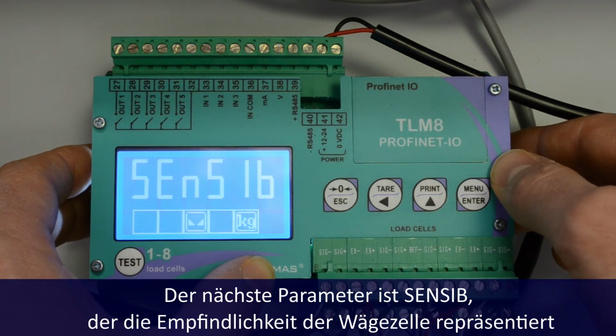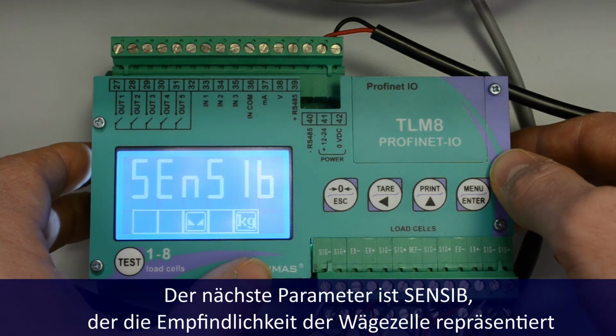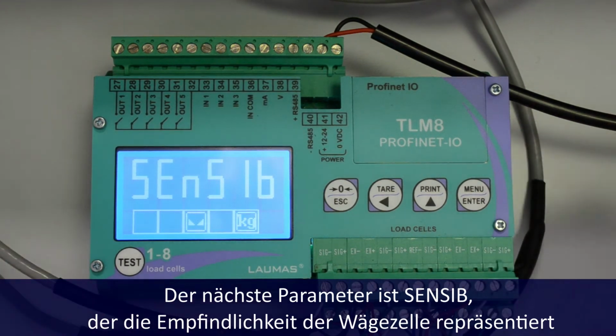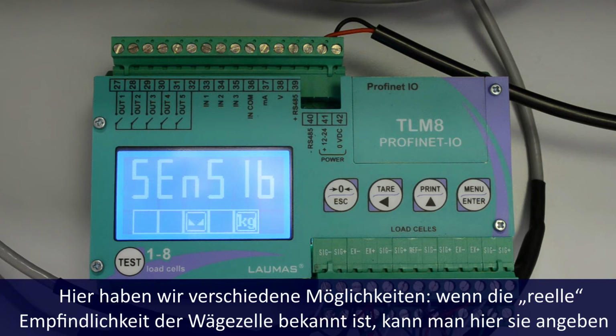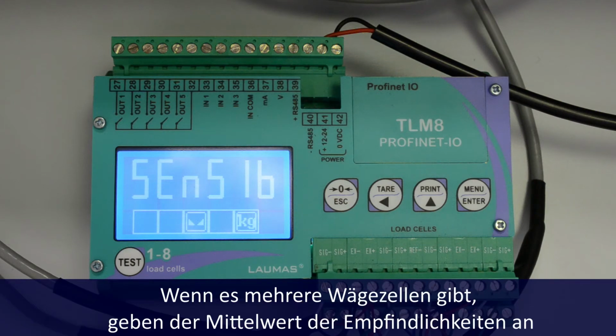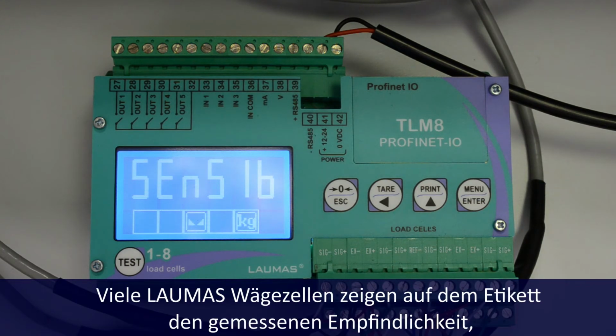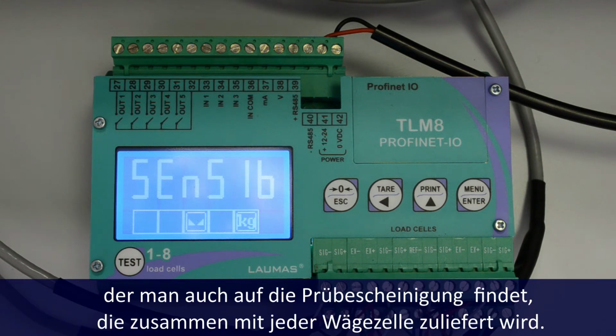The next parameter is SENSIB, which stands for the load cell's sensitivity. Here we have different cases. If you know the measured real load cell sensitivity, you can put it here. If you have more than one load cell, type here the average of the sensitivities. In many LAUMAS load cells, you have a label with the measured sensitivity, and you may also find it on the test certificate coming with every cell.